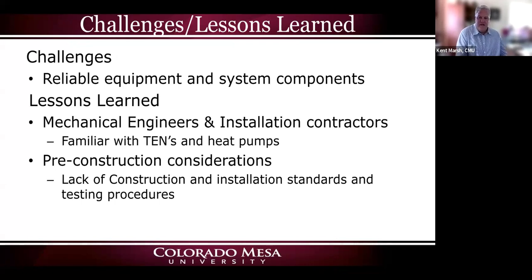Of course, there are challenges and lessons learned. Back in 2007, when we started this process, the heat pumps we could buy didn't like extreme changes in temperature, the delta T, between the central loop or building loop and the interior space. They'd shut off if the delta T got too large. That's since changed, and new technology operates over a much broader delta T spectrum. Also back then, not many mechanical engineers were familiar with how thermal energy networks worked. Now many consultants understand them, far better than I do, and that's changed over the last 15 years.